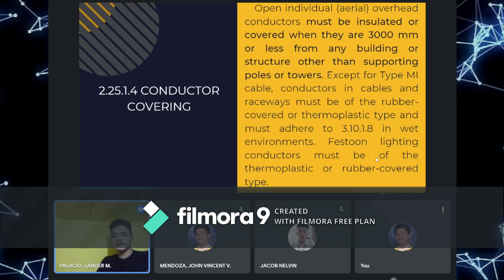Okay, conductor covering. So, open individual or aerial conductors. Overhead conductors must be insulated or covered when they are 3,000 millimeters or less from any building or structure other than supporting poles or towers. Except for type MI cable, conductors in cable and raceway must be of the rubber-covered or thermoplastic type and must adhere to Article 3.10.1.8 in wet environments. So, festoon lighting conductors must be of the thermoplastic or rubber-covered type.